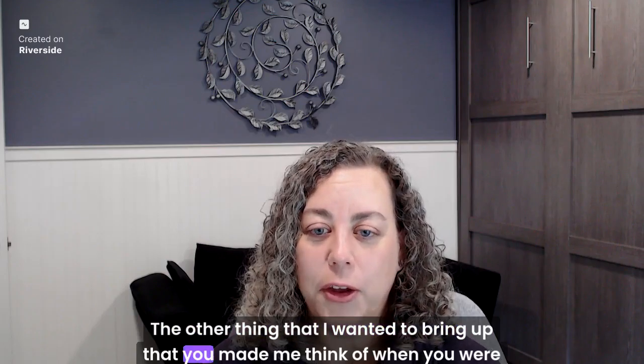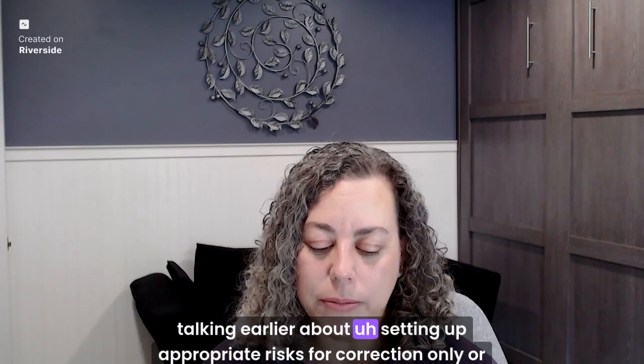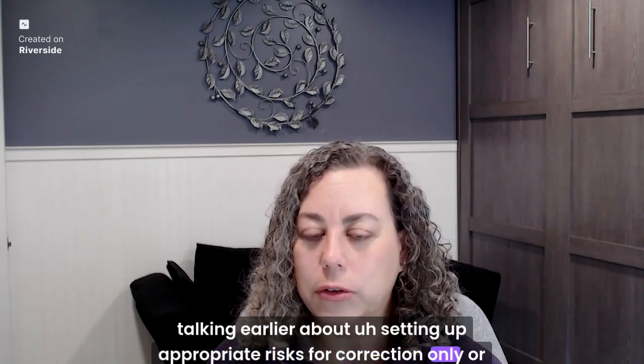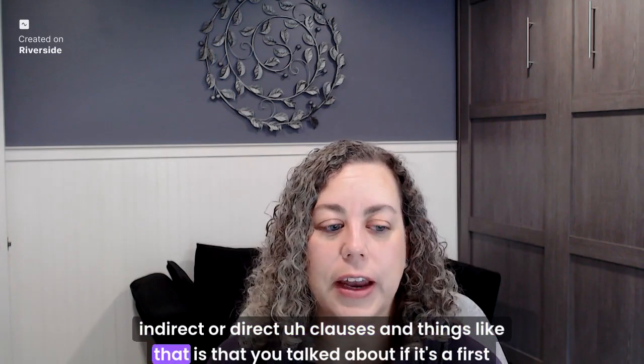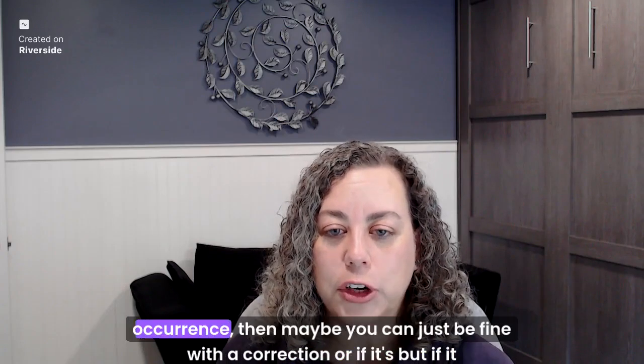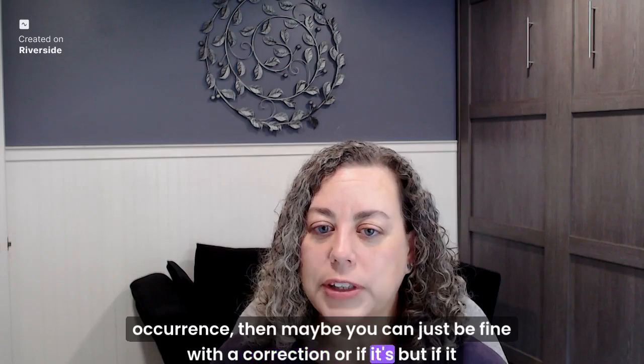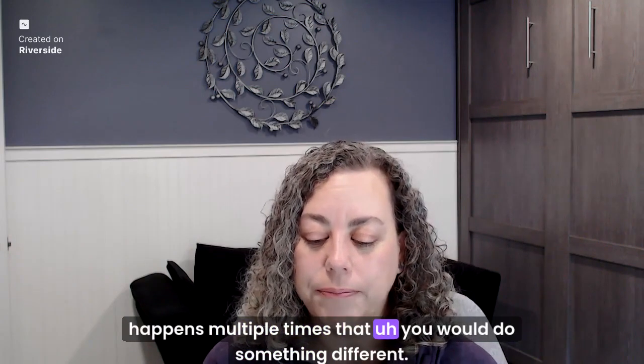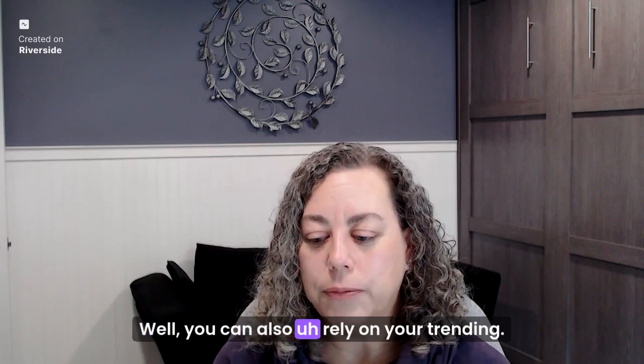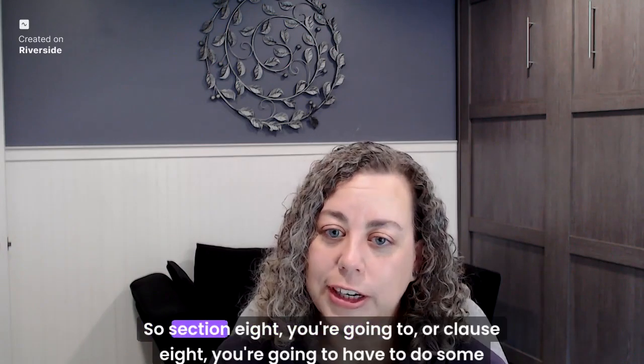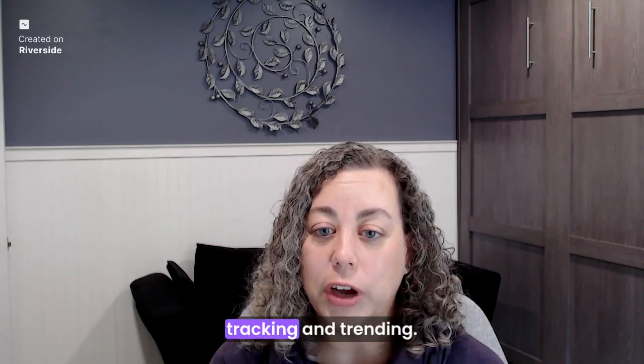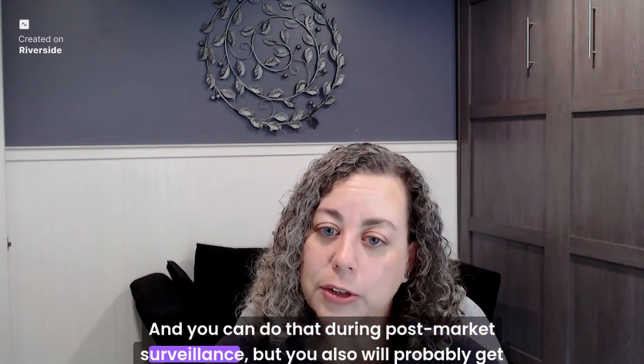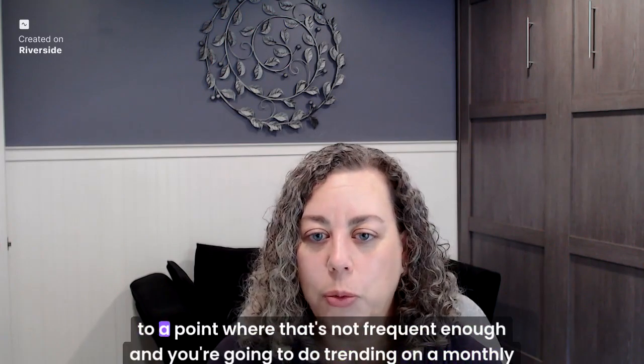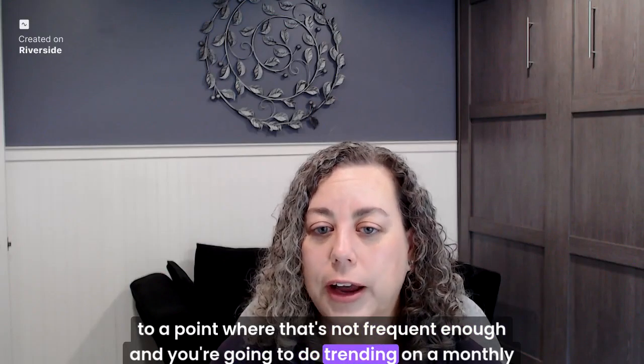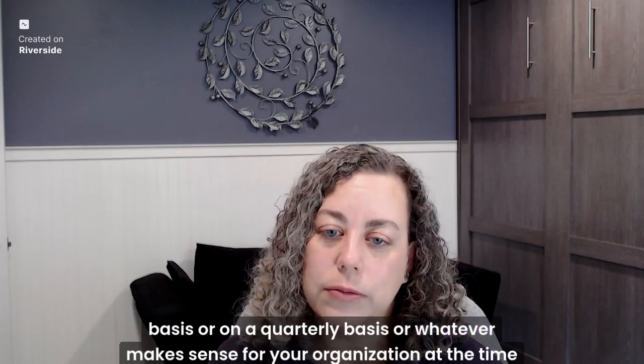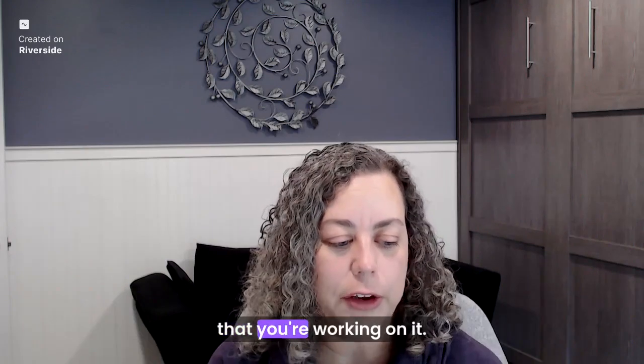The other thing that I wanted to bring up, that you made me think of when you were talking earlier about setting up appropriate risks for correction only or indirect or direct clauses and things like that, is that you talked about if it's a first occurrence, then maybe you can just be fine with a correction, or if it happens multiple times, that you would do something different. Well, you can also rely on your trending activities, right? So clause 8, you're going to have to do some tracking and trending, and you can do that during post-market surveillance, but you also will probably get to a point where that's not frequent enough, and you're going to do trending on a monthly basis or on a quarterly basis, or whatever makes sense for your organization at the time that you're working on it.